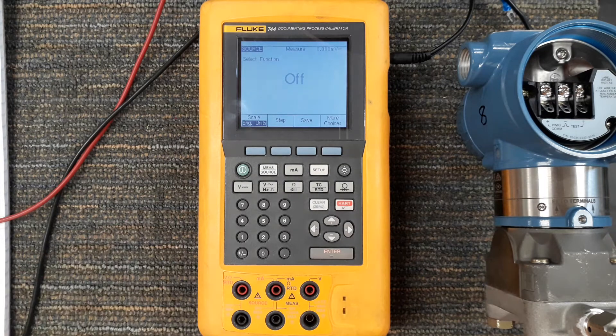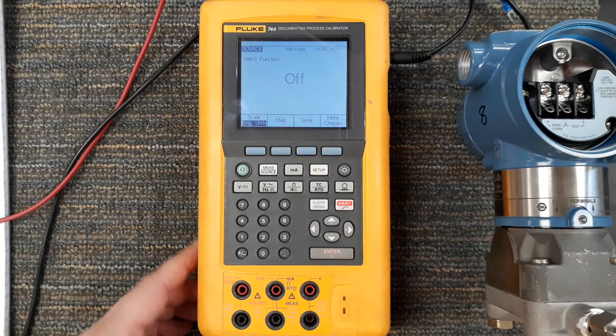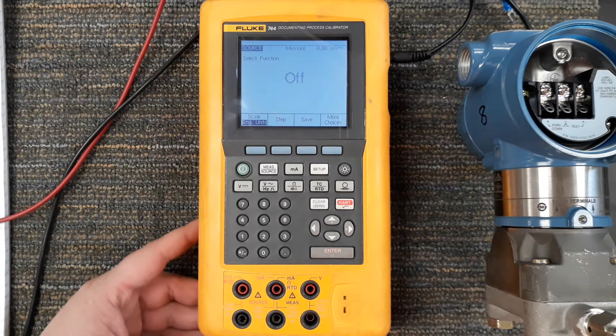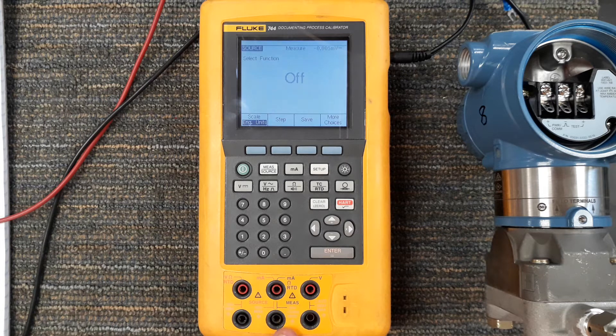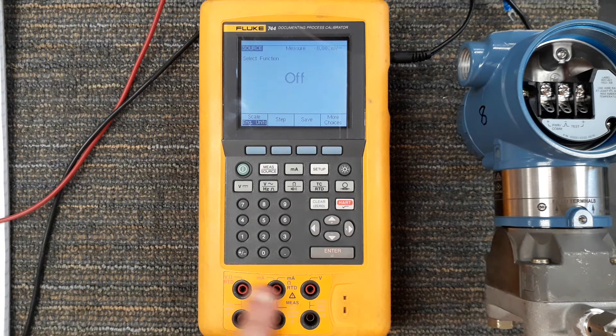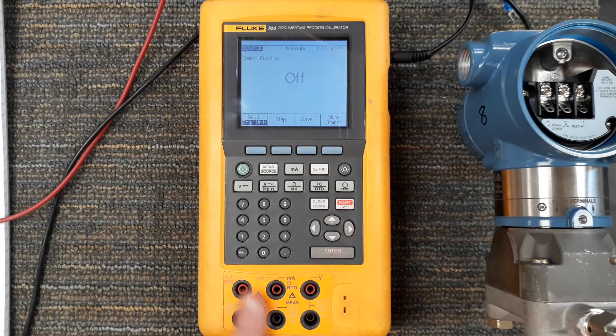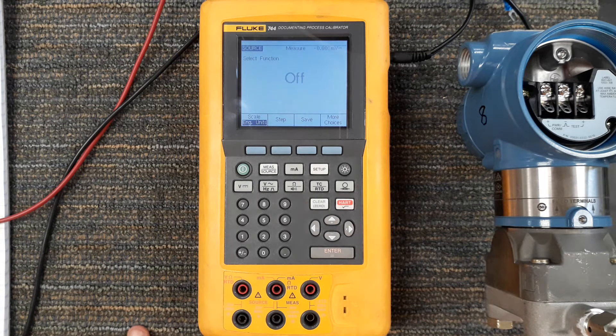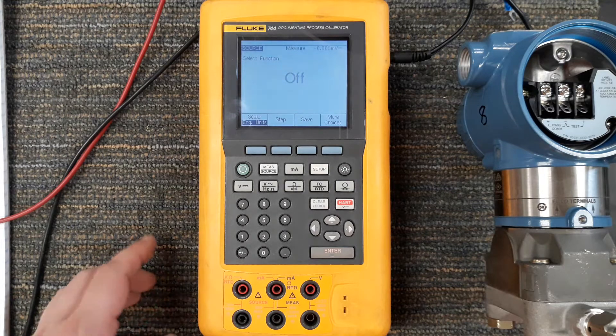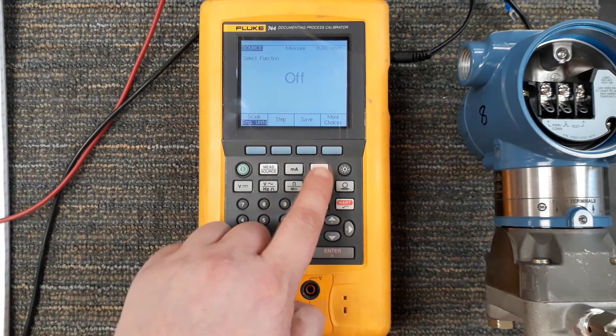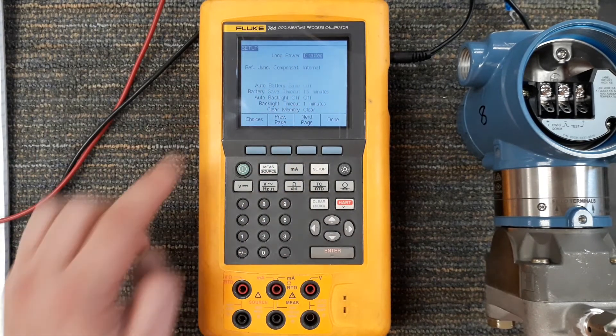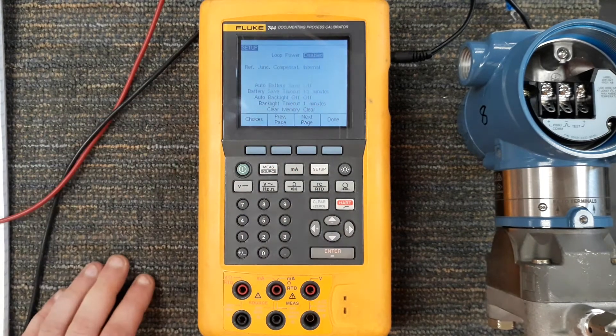First thing I want to bring up is when we're providing loop power a lot of people think oh we're sourcing loop power which we are and we're going to be using down here in the ports as we described in the last video a pair of these red ports over here. Now the confusing part, I'm going to go into setup. In order to provide loop power we have to hit the setup button. It's the very first thing that we can do and it says loop power right now is disabled.